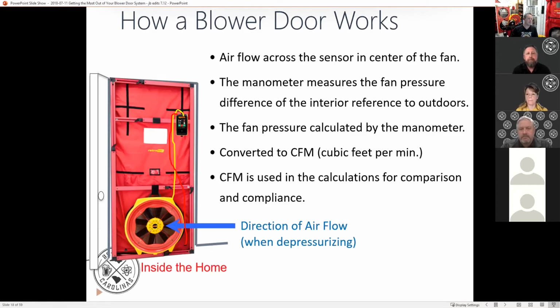But the manometer that we use on this, or the pressure gauge, interchangeable terms, is very high precision. It's not going to be like the common pressure gauge that your HVAC contractor is usually going to have in their bag. These can measure down to a fraction of a pascal of pressure. And if you know about inches of water, there's 250 pascals in 1 inch of water. So these are really, really high precision manometers. And the way we typically test a house, in every standard for residential buildings, is we test at 50 pascals of pressure. That's equivalent to about a 20-mile-an-hour wind on all 6 sides of the house. And so we test all houses to that same pressure just to put them on a common baseline.